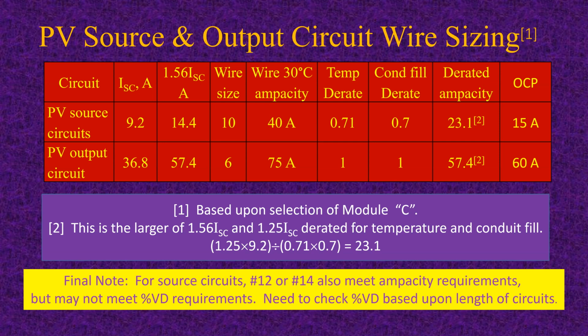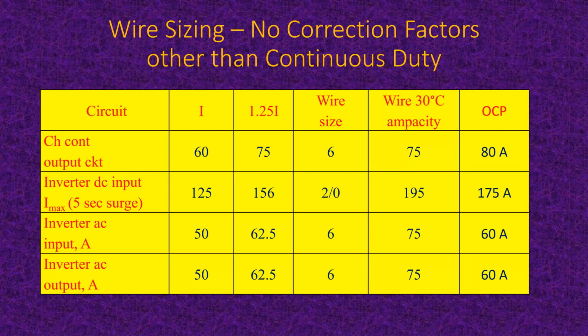So again, if you really are interested in this, you can go through these calculations in more detail if you just order up the PDFs. Okay. The only correction factor we're using here, then just a list of all the wire sizes for the system, and they're based on the continuous duty correction of 125%. Okay, so this is typical wires and circuit breakers you're going to be using for this particular setup.